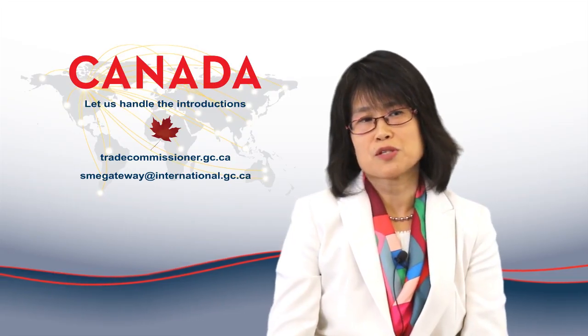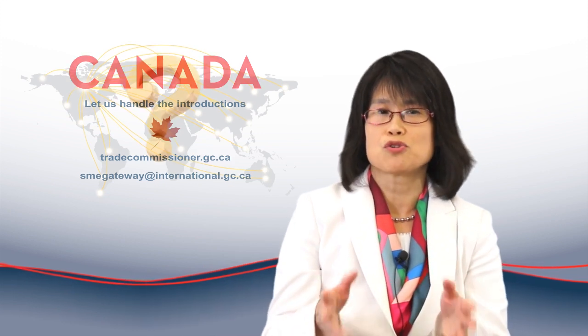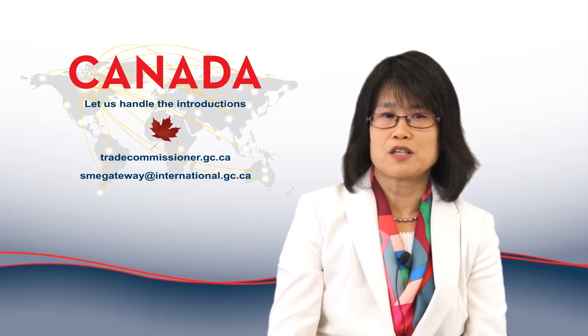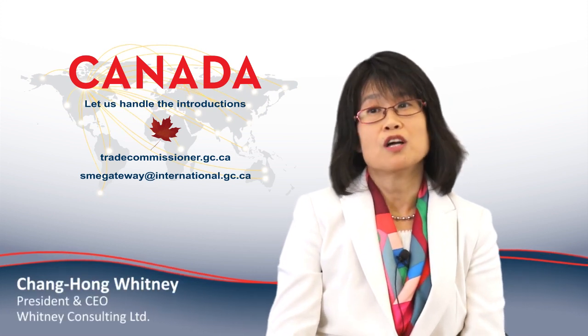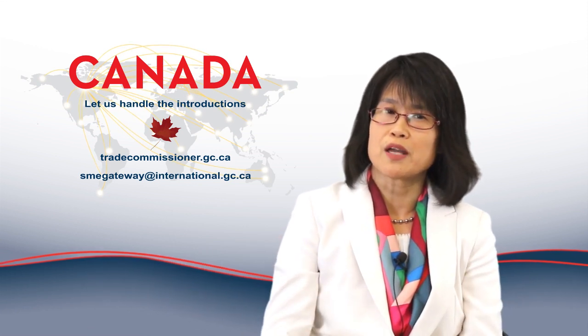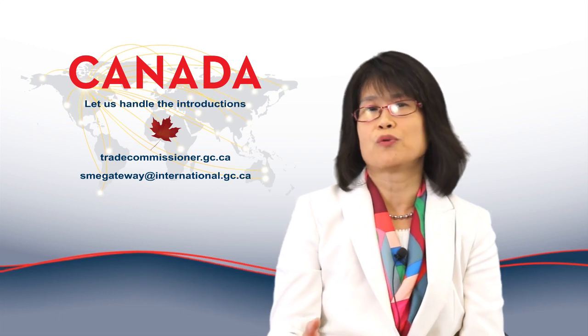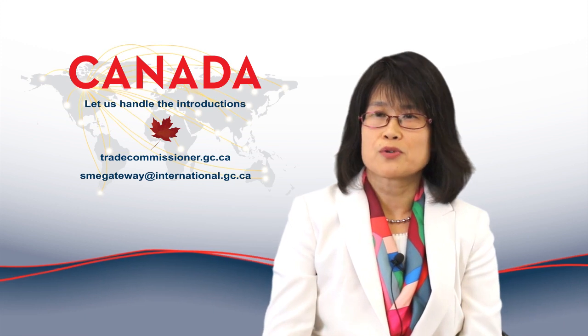Sometimes companies have a new product and cannot find a suitable classification in the existing CFDA system. There is a process to apply for classification through CFDA agencies; however, that process takes about six months or more — a big chunk of time. So there are a lot of strategic decisions: do you apply for a new classification, or work with what's available?